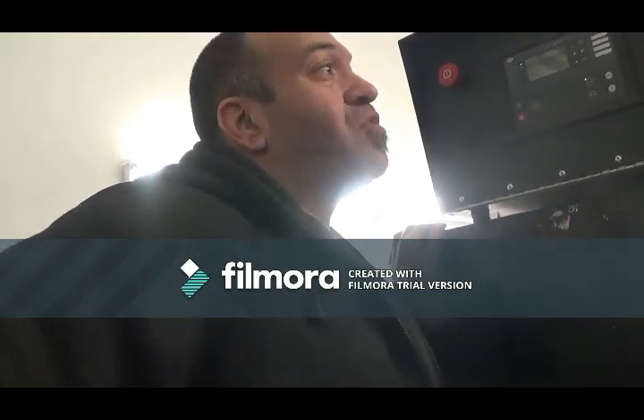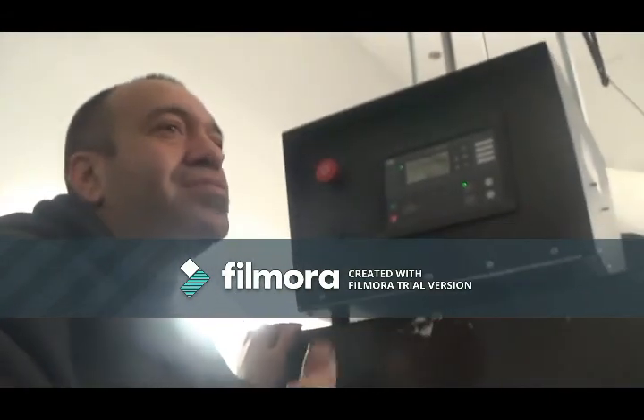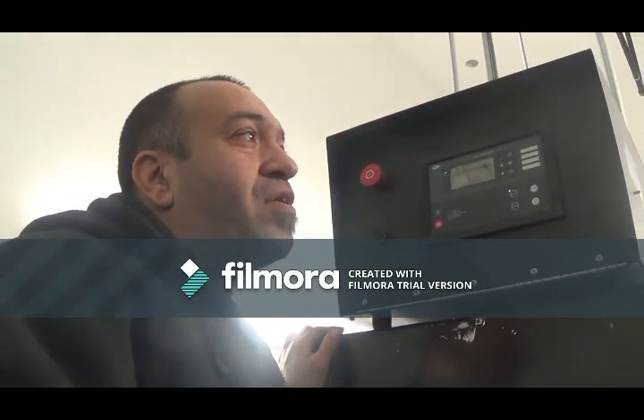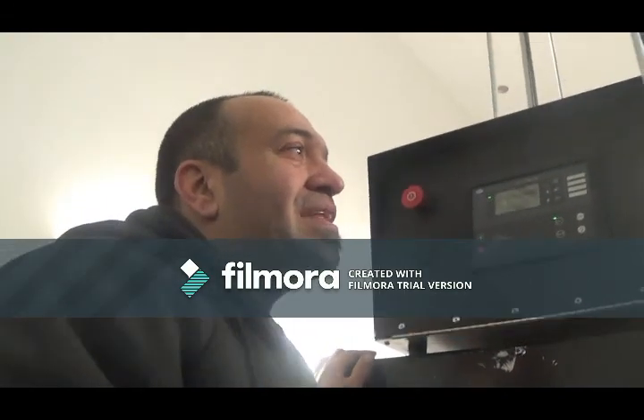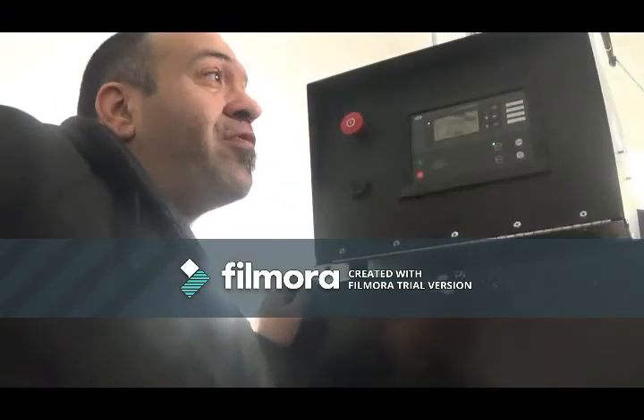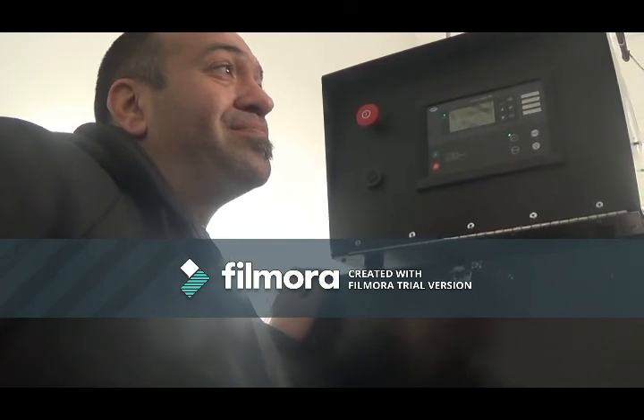We will suggest it most likely. When we come to the service, no matter what, eventually a technician will suggest it. Once we open inside, if we see the lugs are the type that wear out easily, because different companies supply different lugs, believe me, sometimes it's cheaper to put a cam lock in it than to keep changing this over and over. We're talking here on the order of a few thousand dollars. Yeah, at least. Okay, but so are we good now with the system?